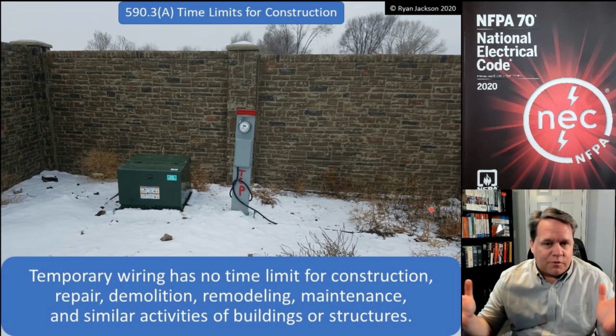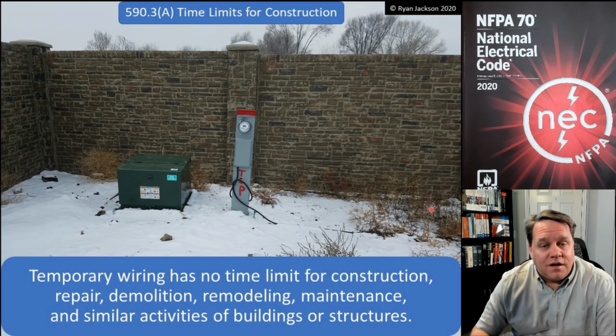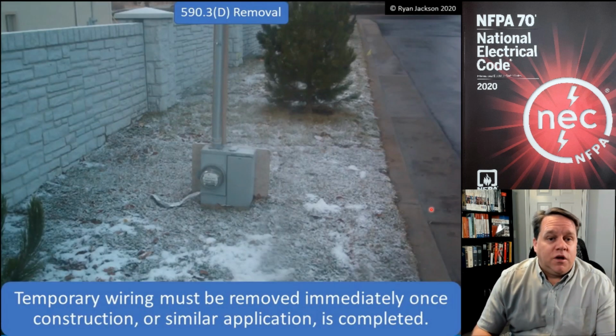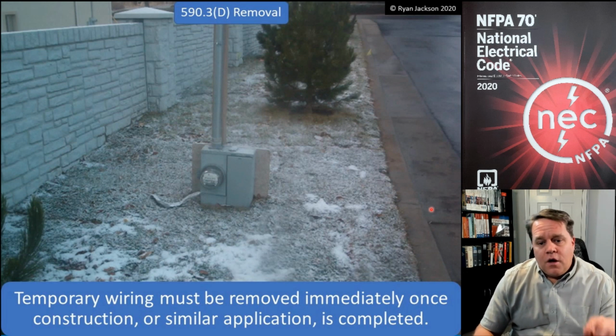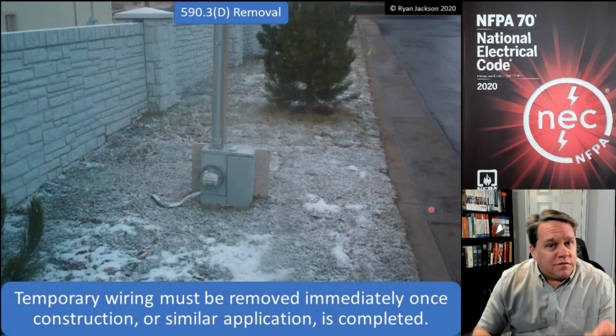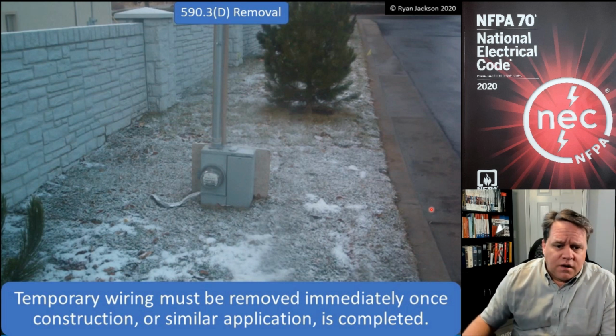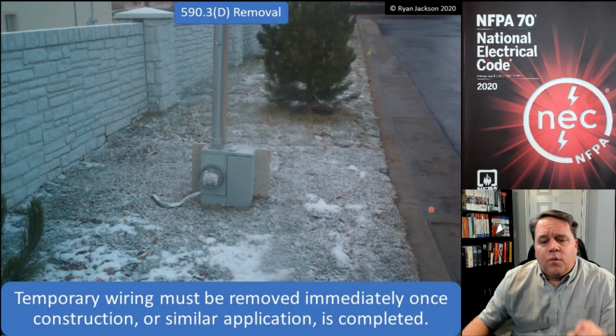You can have your temporary wiring up as long as you need it, but if we keep reading and we go to subsection D, it does have to be removed once the job is complete. So 590.3(D), temporary wiring must be removed immediately once construction or a similar application is completed.